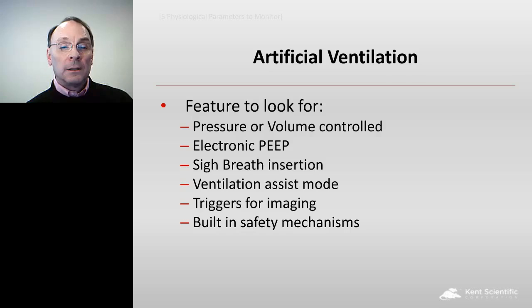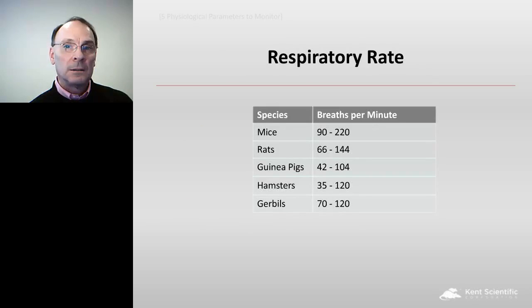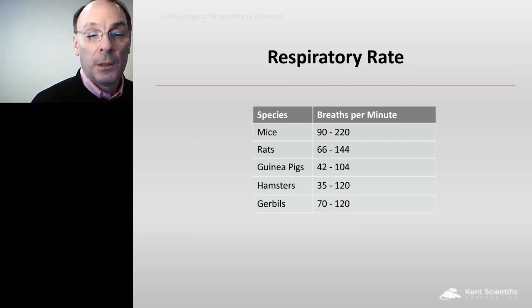Also, if the animal is lighter, have a ventilator that has an assist mode in it so that it detects when the animal is trying to inhale, and then it will give the animal a breath. And also, if you're doing imaging, you'll definitely want a ventilator that triggers and works with your imaging, your MRI machine or something like that. And make sure it has built-in safety parameters, like it can't do overpressure. Standard piston pump type ventilators, the old type, with the piston pump going back and forth. A lot of people have used those through the years, but they've never monitored the animal's airway pressure. So if a person dialed in the wrong tidal volume in the piston pump, the airway pressure would go way up and could often pop the lungs.